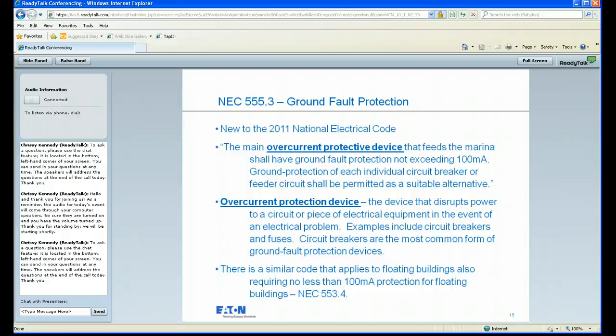Again, this is new to the 2011 National Electrical Code. I'll read this verbatim. The main overcurrent protective device that feeds the marina shall have ground fault protection not exceeding 100 milliamps. Ground protection of each circuit breaker or feeder circuit shall be permitted as a suitable alternative.